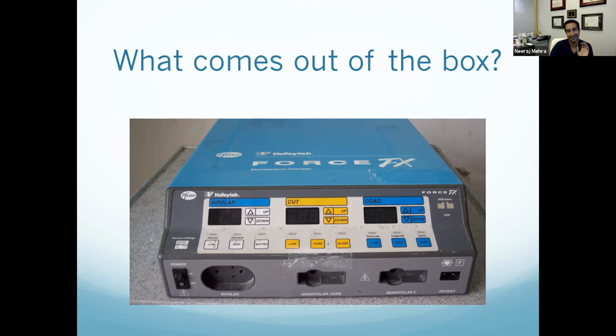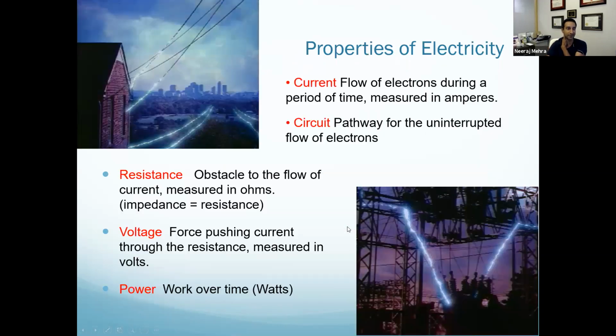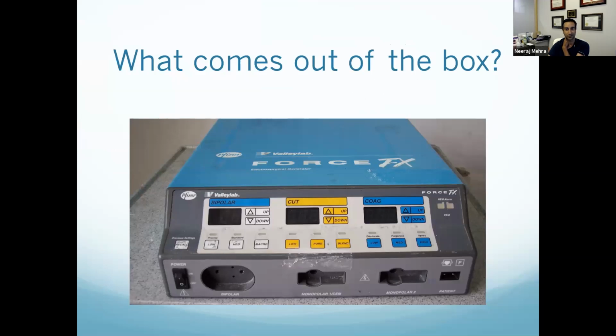So everyone's wrong. The answer is watts. When you set the number here, voltage is the force, power is the watt. So what you're setting is the power setting — the amount of watts going through the electrosurgical unit and through the patient. That's important to know as we understand the later principles. And it's important in your dictation — you should start putting in your dictation that you used an energy setting of 30 watts.